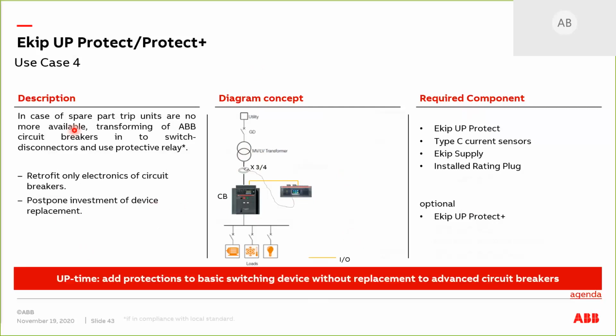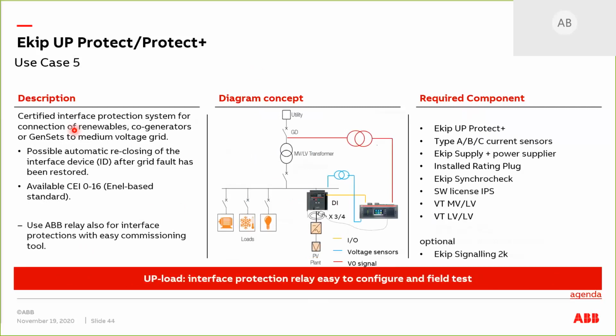Okay, and then this is more of a complex scenario. This one is the interface protection system for the connection of renewables or a co-generator or the generator itself. What will happen is that we will have to monitor the side of the utility and also the low voltage side. And from those embedded logics, we will know whether we need to trip the breaker or not.